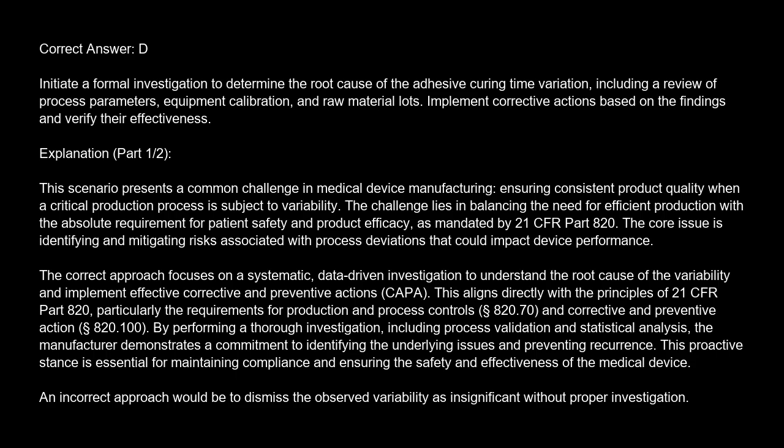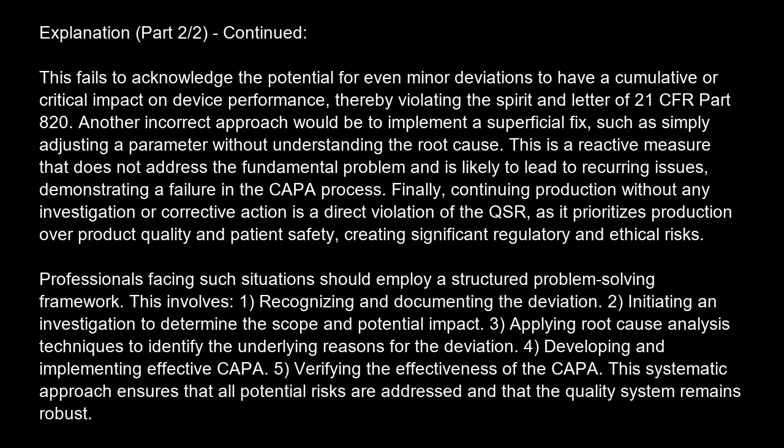An incorrect approach would be to dismiss the observed variability as insignificant without proper investigation. This fails to acknowledge the potential for even minor deviations to have a cumulative or critical impact on device performance, thereby violating the spirit and letter of 21 CFR Part 820.